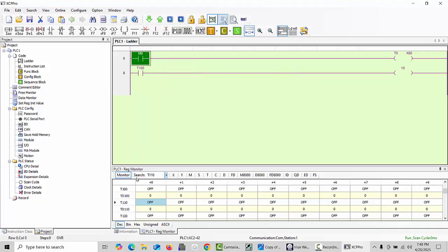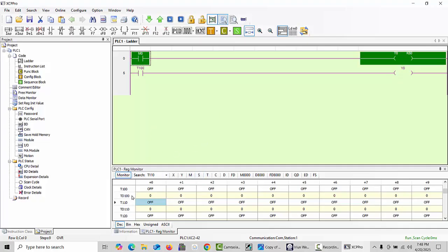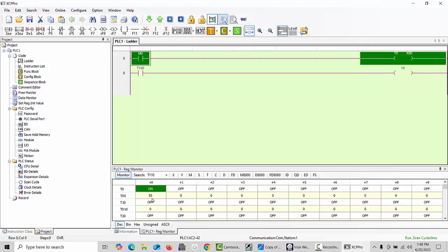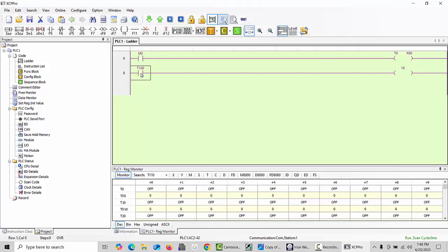Click run mode again — the time is 50 seconds. When you make it on and open ladder monitoring, you can search the timer here. You can see the timer is running. Now I noticed a mistake: upside the timer number was changed to T100, but the output contact was still showing T0 and was not changed. So you have to change that to T100 as well, then click Enter and download again to the PLC.